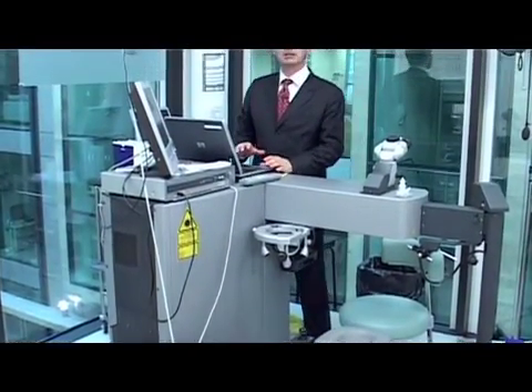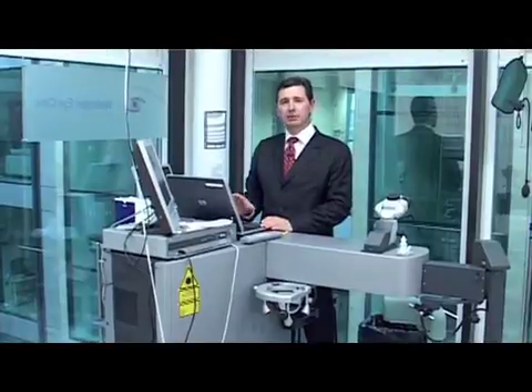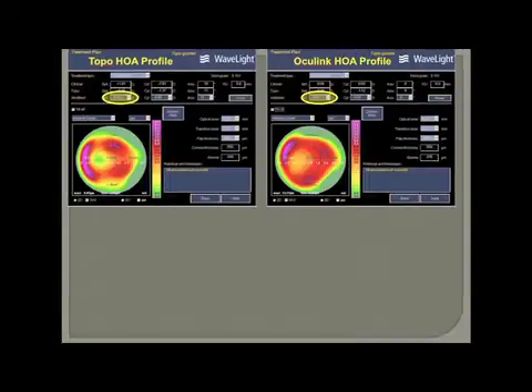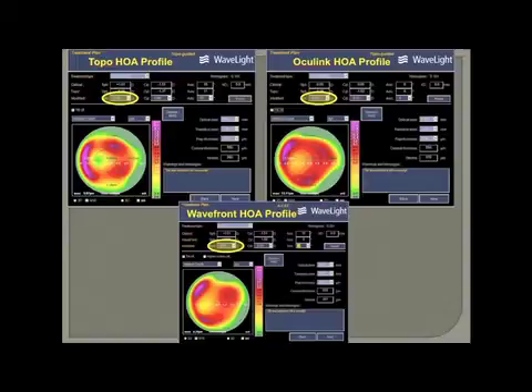I'm now going to show you how we calculate the ablation profile on the Portal software. The upper left image shows the higher order ablation profile based on topography data. The refraction has been modified to zero, and hence this ablation profile is what is going to treat the visual quality issues that the patient is experiencing. The image on the right is based on Oculink data, and the image below is based on Wavefront data. One can see how similar these higher order ablation profiles are, and in this particular case it doesn't matter which profile is used, as they are all going to have a very positive outcome.